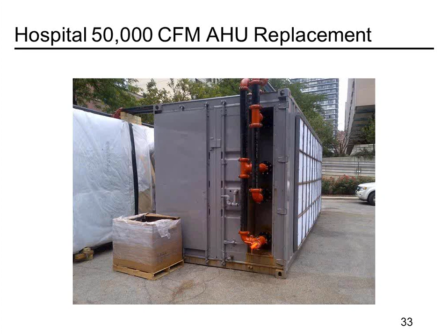This was tied into the space to supply the outside air, to meet the outside air requirements for the hospital while they replaced their air handler over the summer. You can see that they elected to hard pipe everything. In a lot of hospital applications, they like to hard pipe things, especially if they have some lead time on it. And you can see it's pretty nice looking, with the Victaulic piping and the duct on the left there.